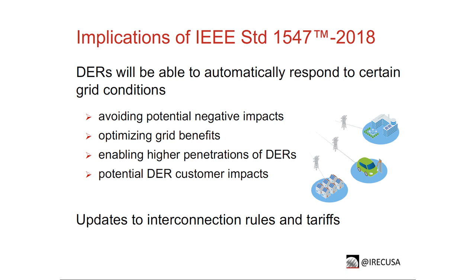The next step already underway is the publication of IEEE 1547.1, the conformance test procedures for equipment, basically what all the equipment will be tested to. Then Underwriters Laboratories will quickly update the inverter product safety standard 1741, working closely with IEEE to do that. From that point, tested and certified 1547-2018 compliant DER products will be available on the market by 2021 or 2022.